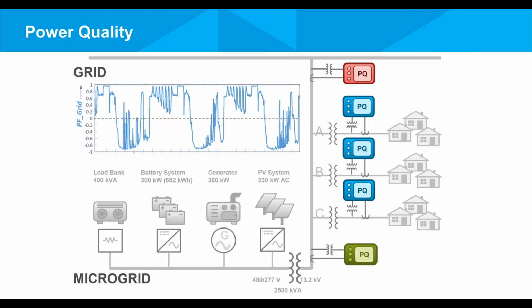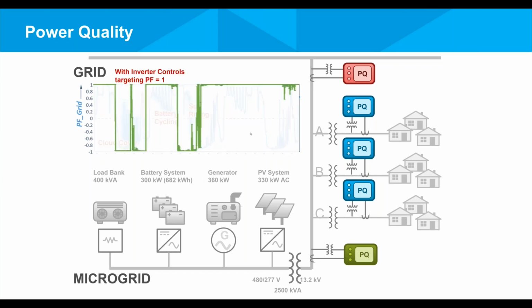But in this case, the power factor is erratic. And what is the cause of this erratic nature of the power factor? That's primarily cloud covering when solar is generating power, battery cycling, and also ramp up and ramp down of solar, sun rising or sunset. Those contribute to the erratic nature of the power factor. But when the inverters are set to control the power factor, this is what it looks like.